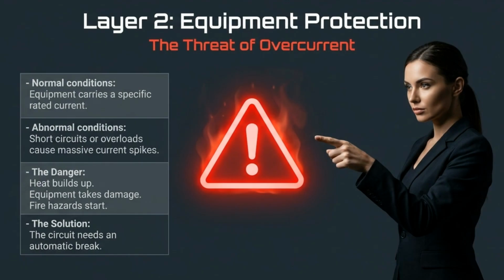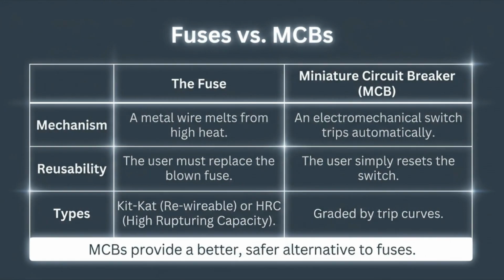Layer 2 is equipment protection against overcurrent. Abnormal conditions like short circuits cause massive current spikes, leading to heat buildup, equipment damage, and fire hazards. The solution is an automatic circuit breaker. Miniature circuit breakers, or MCBs, are a safer alternative to fuses.